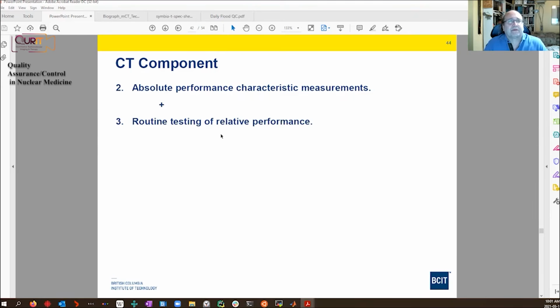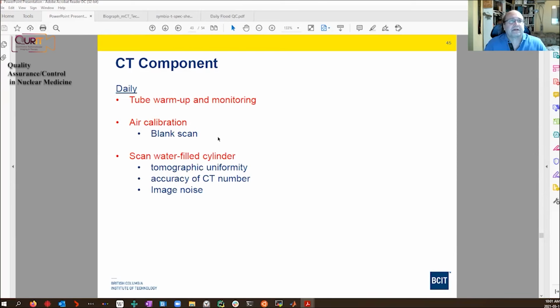I'm going to put some of these performance characteristics for CT together. Daily, there are different tests involving warming up the tube and doing an air cal, which is a blank scan with nothing in the scanner, and looking at the sinograms or reconstructing it to see if there are any detector-to-detector variations or non-uniformities, similar to what I showed with sinograms in PET. Again, this varies with scanners, so don't count on this covering all scanners.